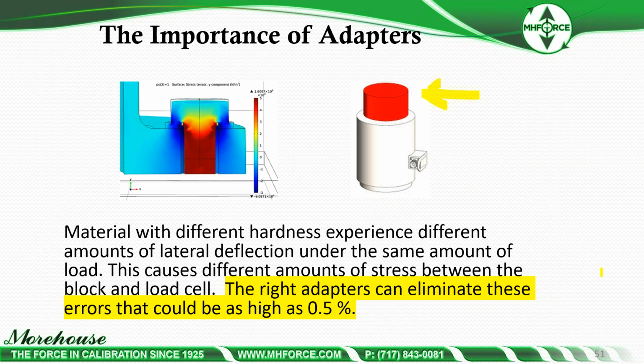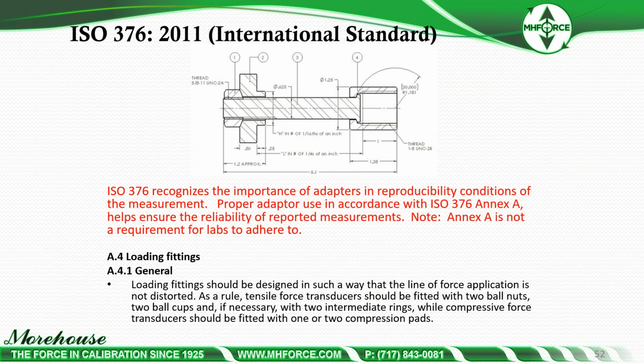Our preferred approach, if we're making a top block, is sending it out to be heat treated to give better safety factors, and it makes the results much more reproducible as far as rotation. We get much better numbers if we use a hardened adapter on the top of the load cell. For ISO 376, we'll talk about their recommendation for compression adapters, but first we're going to talk about tension adapters.